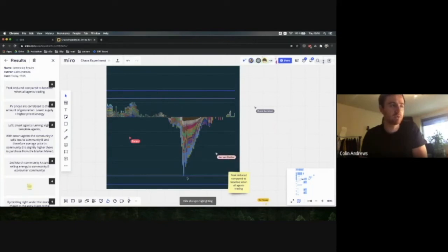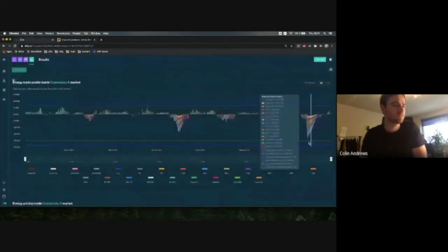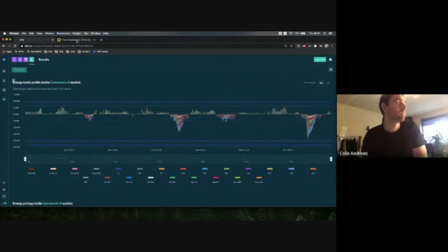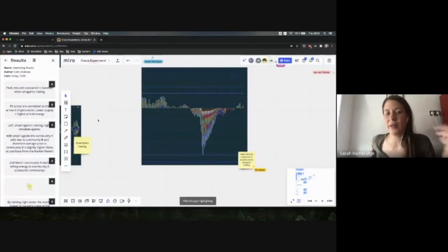And this is the highest peak for the PVs. And it looks like the total peak, if we go into the results, was about 3 kilowatt hours less than the baseline peak export. So it's from 23 kilowatt hours down to 20 kilowatt hours. Right now, we don't have grid fees set up to do that, but it's probably helpful for them to see how the financial incentives they may be seeing impact the behavior on the grid.